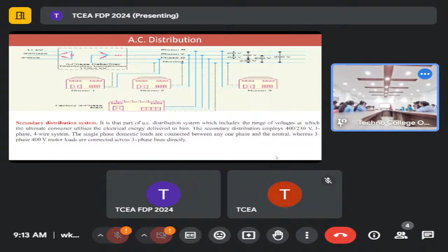From the protection point of view, this is good. We have some star transformers at the transmission level, not at the distribution level. Protection point means schematics. What kind of schematics are you going to implement? For that, a star transformer is also necessary. We have star transformers, but at the 132 kV level. Is it clear?